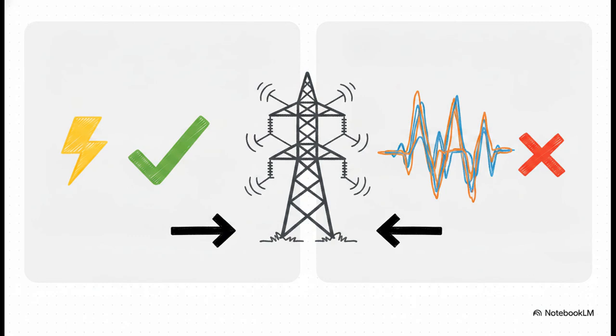So here's the real myth versus reality check. Your voltage can sit perfectly within its legal plus or minus 6% band, and your installation can still be utterly non-compliant. Why? Because clean power is about waveform shape and balance too, not just magnitude. You could have the exact right amount of voltage, but if it's being delivered in this inefficient, lopsided way, you are creating a massive headache for the wider grid.